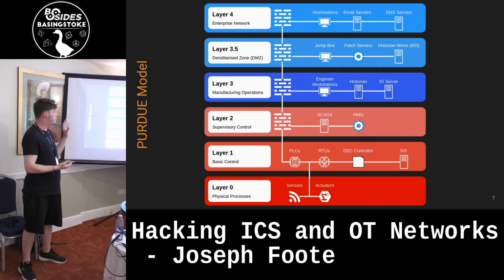Level 3, you have manufacturing operations, so that's in the middle. Your engineering workstations, your main, primary historian, so that has read and write access, and file servers and other bits. But let's focus on engineering workstations for a second. The engineering workstations are where technical individuals who have the authorization would be able to land on the network from that workstation and access parts of the OT environment, bits that are most critical. Again, very selective and has to be secured.